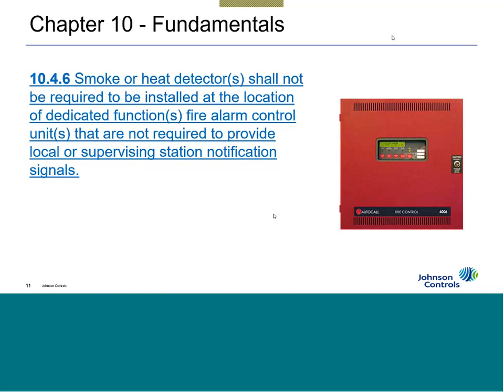Where's your one pull station that's required? Well, it's a dedicated function. Where are the horns, your strobes, and all the rest of that? Well, that's not what it is. It's just a dedicated function system. How do they know that? So you have to call it a dedicated function control unit. Because it doesn't have a signal that needs to be sent to the occupants or off-site, you don't need to put a smoke detector or a heat detector above that control unit. So hopefully all that makes sense to you.